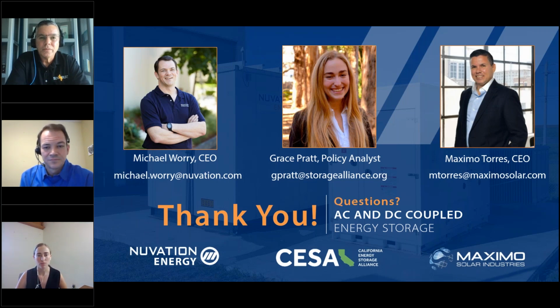Awesome. And Michael, I think you touched on this in your presentation, but someone did ask what the consequences are on transformer design between the AC and DC coupled systems. Yeah, so in a transformer design, the transformer is some 99% efficient. And in a DC coupled system, you don't need any transformers on the DC side. Transformers are just an AC bus component. And it's usually for when you want to go longer distances.